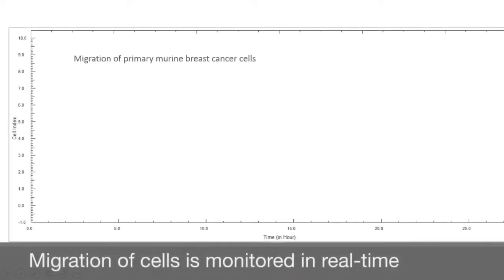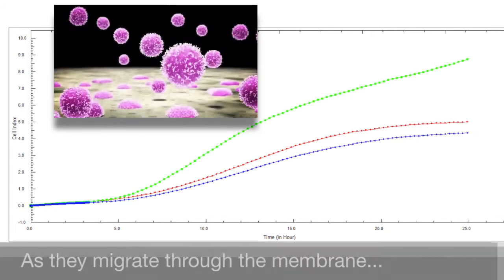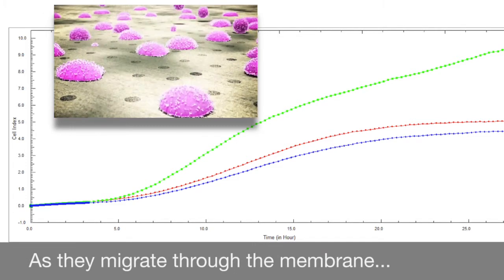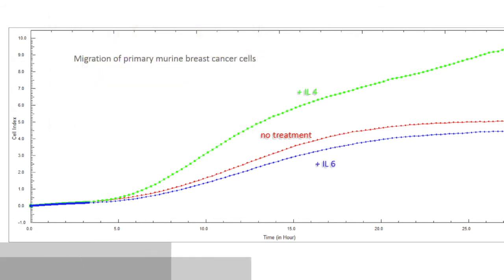Cell migration is observed in real time. As cells pass through the membrane, a very low alternating current flows through the electrode network without affecting cell status and viability. The detected impedance value will be directly proportional to the number of migrating cells that have adhered to the electrode surface.